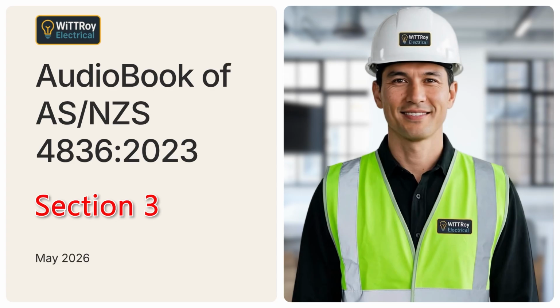If more than one person needs to attach a personal lock to the same isolator, a suitable multi-lock device must be used. The safety idea is very important. Each worker protects their own safety with their own lock. The equipment cannot be re-energized until every person has removed their own lock.